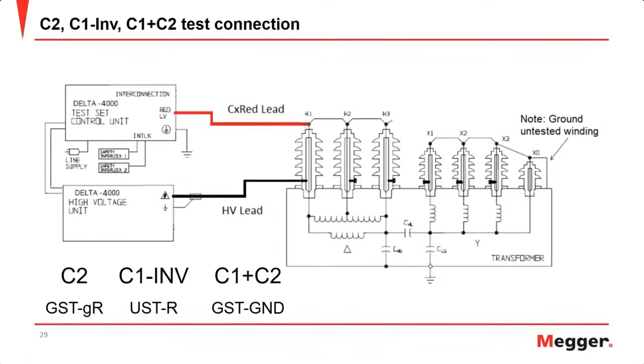If it was a dry type transformer, then yes, you may see the power factor values change as you increase voltage, since there's no oil inside the voids within the paper. So you will get some partial discharge as you increase voltage. But for OIP bushings or transformers, testing at 500 volts or 10,000 volts, you should get the same value if the insulation is in good condition.